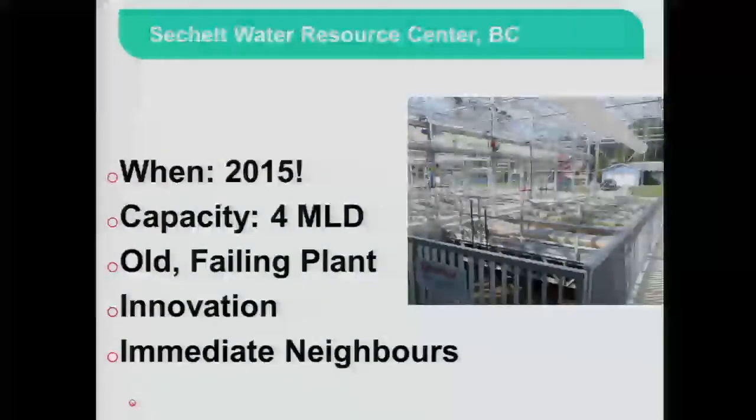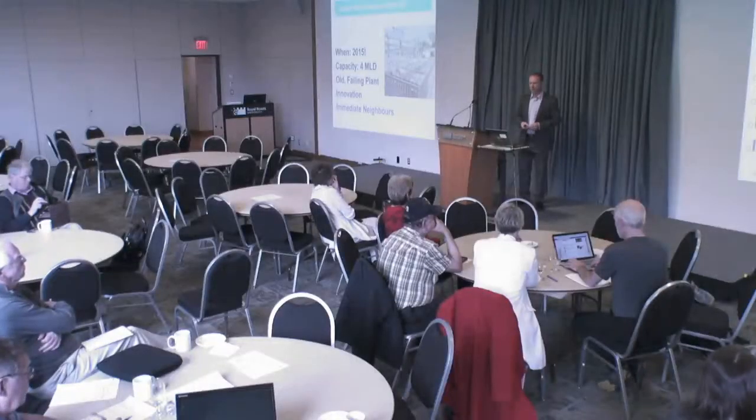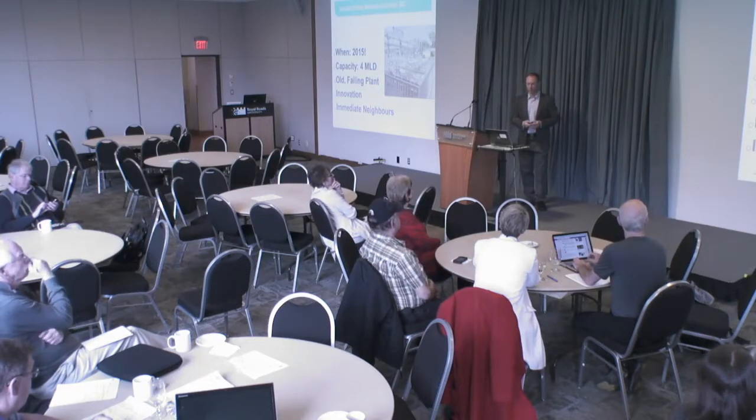So the case study I'd like to present on this is the wastewater treatment reference, which is in Sechelt, on the Sunshine Coast. So this became operational, well, now, basically. We are in performance testing as we speak, and in the process of handing over that treatment plant to the municipality. The existing plant, which was called the Ebbtide wastewater treatment plant, was failing for various reasons. It was old, it was mechanically getting to the end of its life, didn't have the capacity that the community needed because of growth in the community, so it needed to be expanded, and it wasn't achieving the latest effluent quality standards, federal standards, 25 milligrams a litre TSS-BOD.